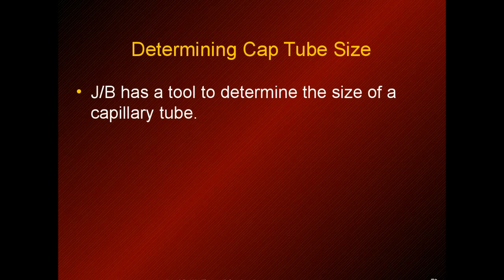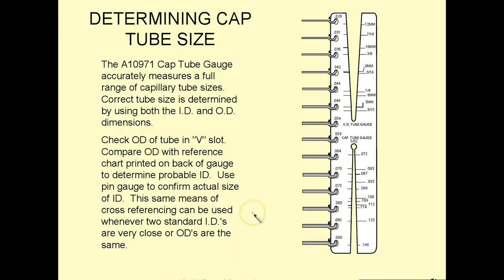If you can't find the size of the cap tube on a system, there are cap tube diameter checkers. You slide the checker over the tube to check the outside diameter, and use the little keys to slide into the cap tube to determine the inside size. That's it — about 15 minutes on the capillary tube metering device. Any questions, please email or get on the free student forum.